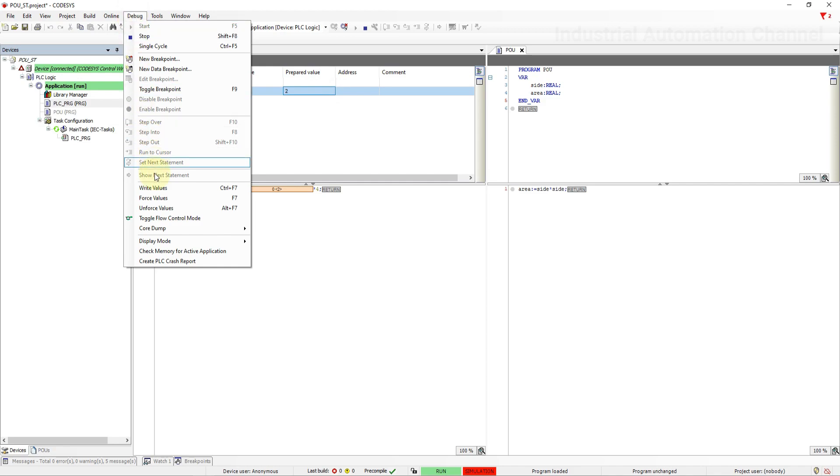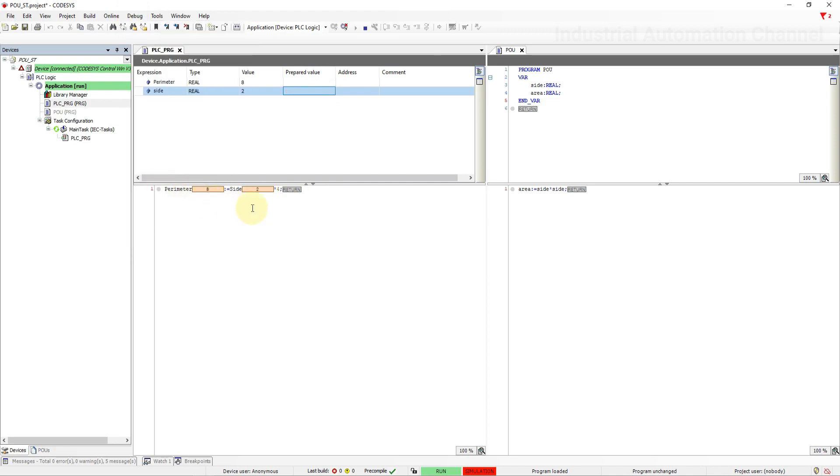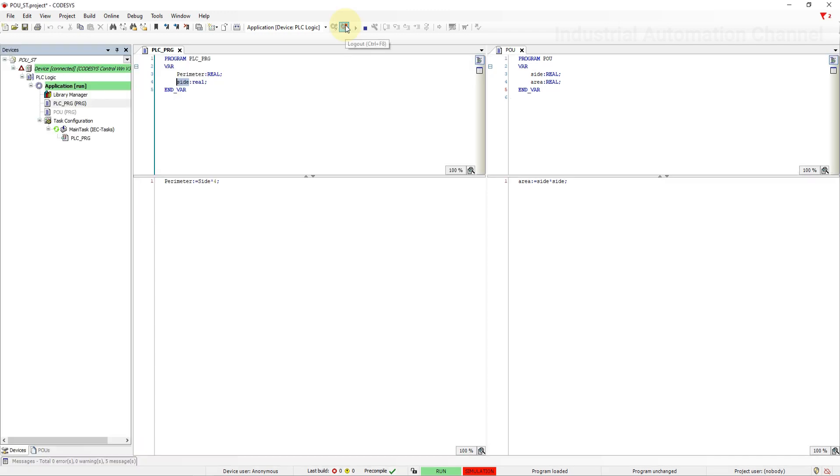Here what you should notice is that this newly created POU has not been automatically added to the main task of the PLC. So it is not scanned. That's the point that we have to call the program when we have created a new one. You can call programs inside a task configuration or on different programs functions or function blocks to create tasks.